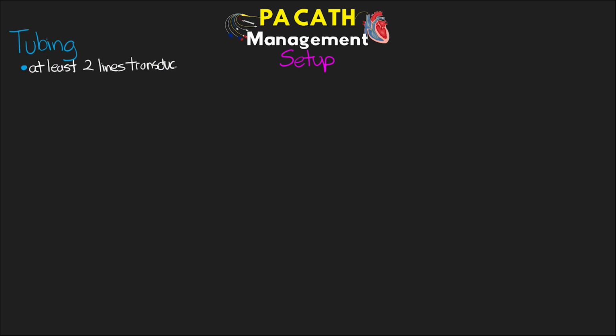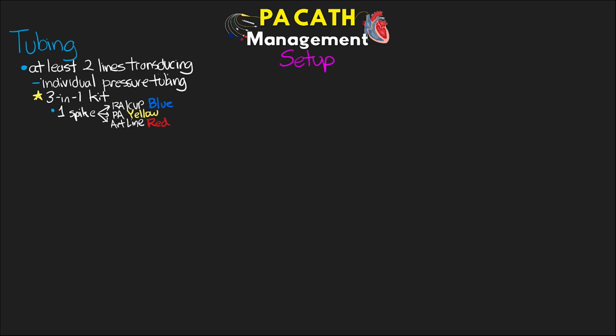that we're going to be transducing. Now, while we can use individual pressure tubing lines, they actually have these kits that are like a 3-in-1 kit that are designed specifically for PA catheters. They've got 1 spike for 1 pressurized bag of fluid, and then that splits off into 3 lines. We've got our RA CVP, our PA, and then the third one is for ART line. Now, they certainly are nice as they are more organized, and they either have pre-colored parts and stopcocks, so like blue, yellow, and red, or they have stickers that we can apply to the transducer and the lines to easily identify which is for what.